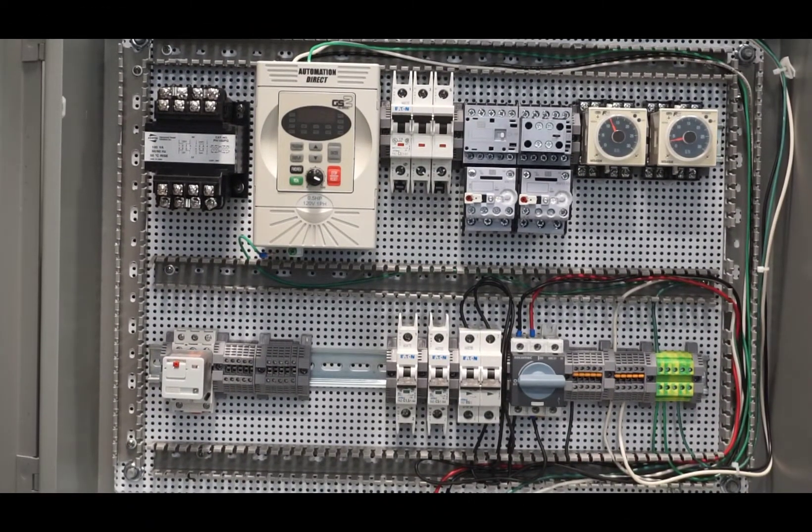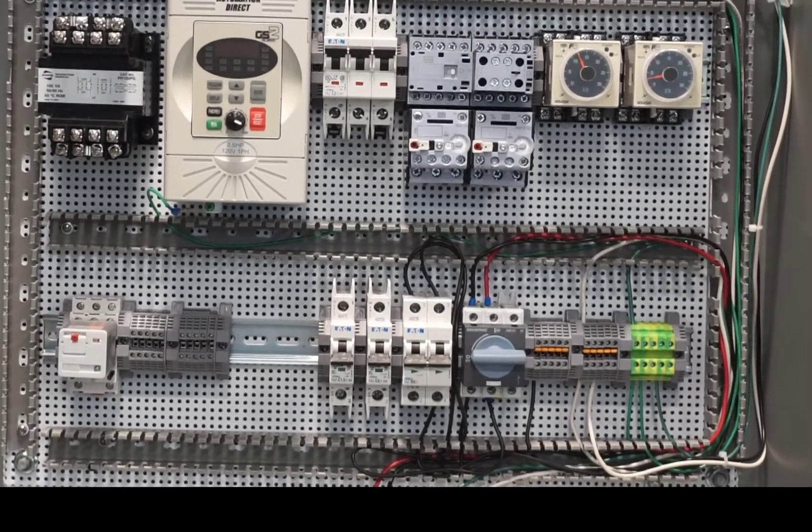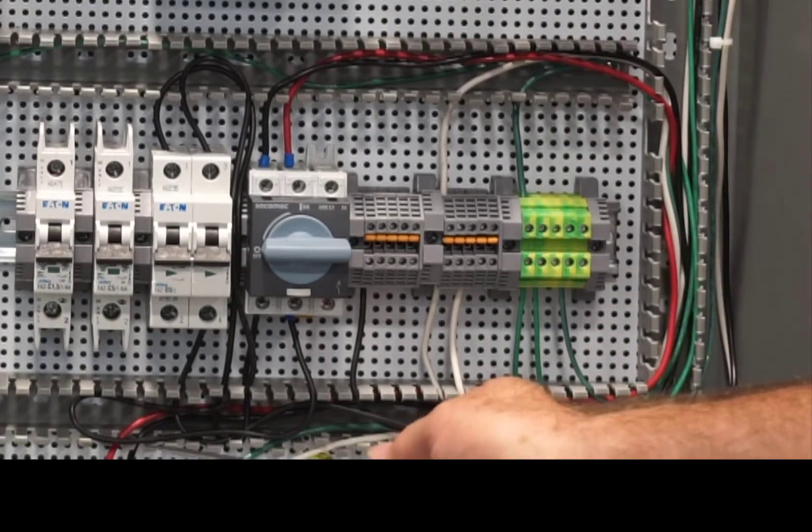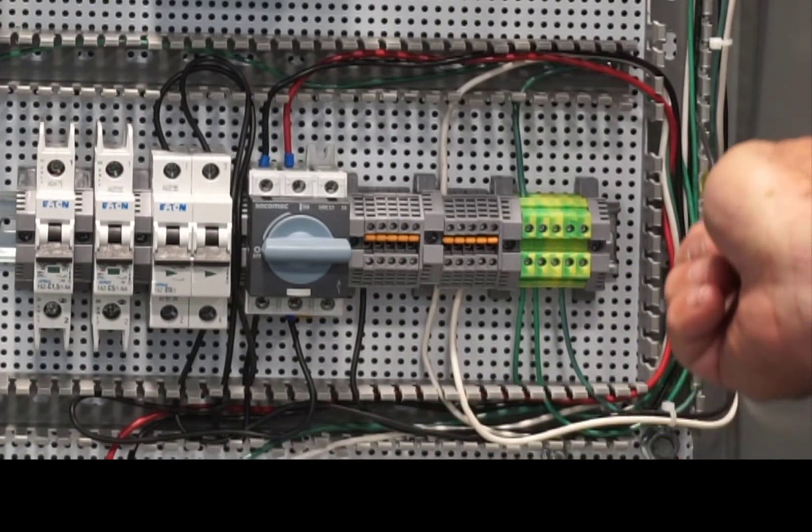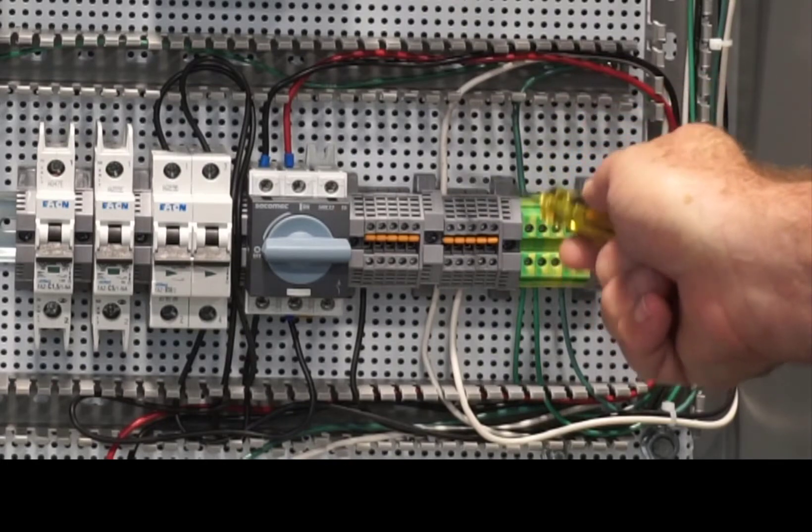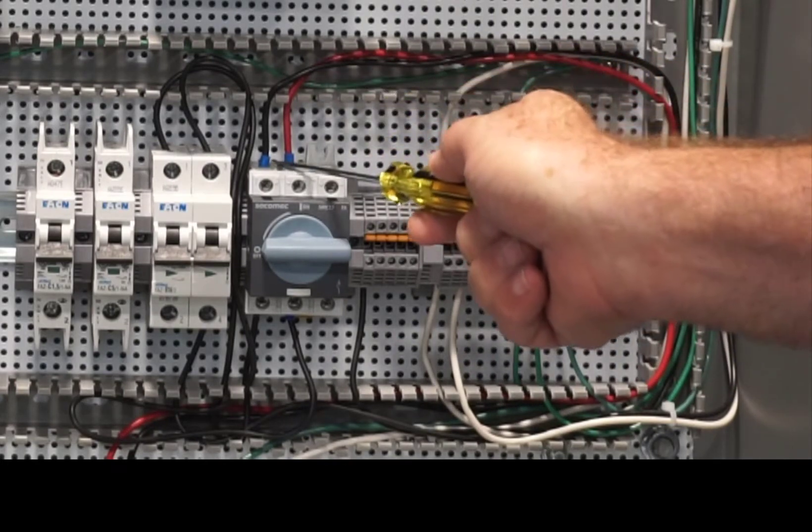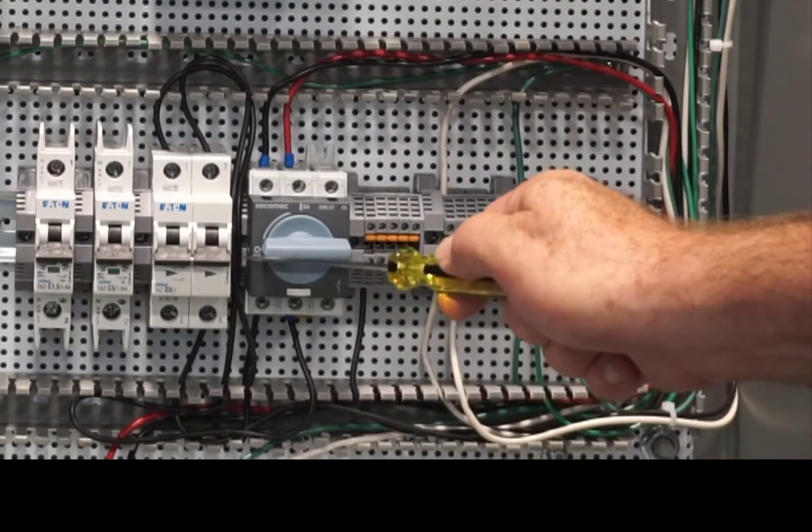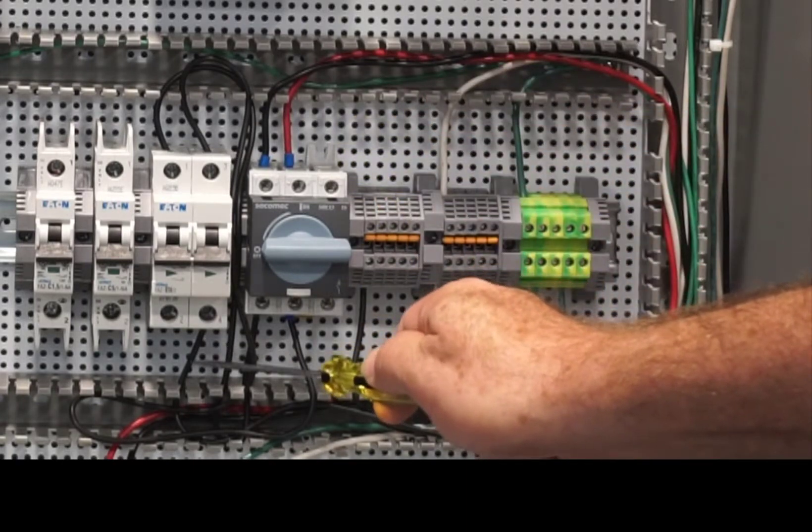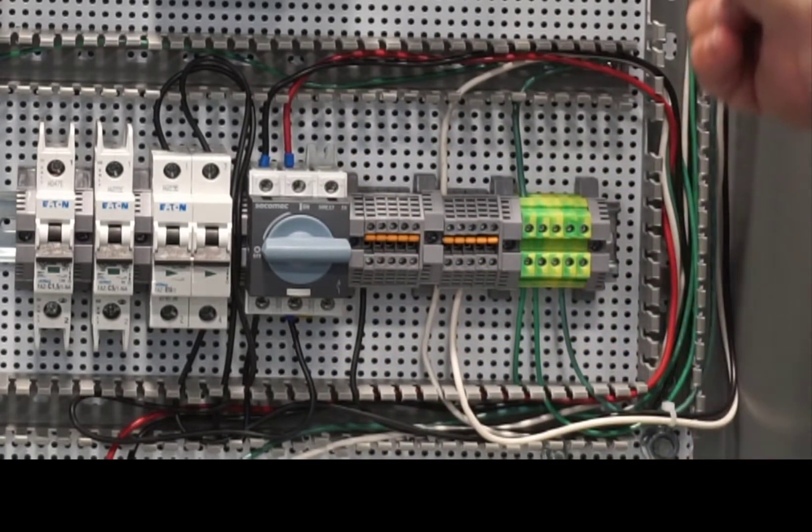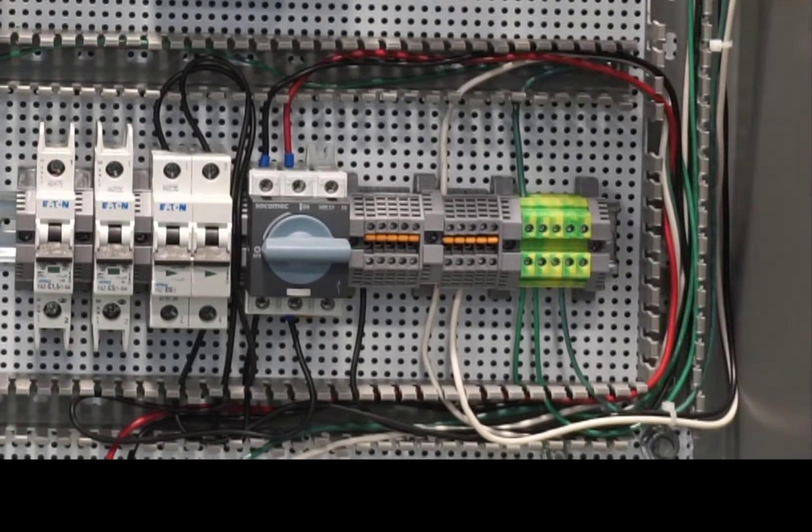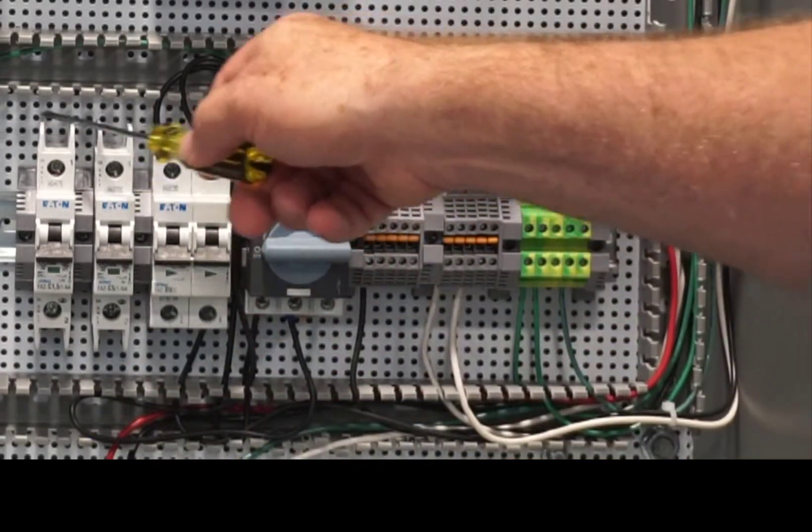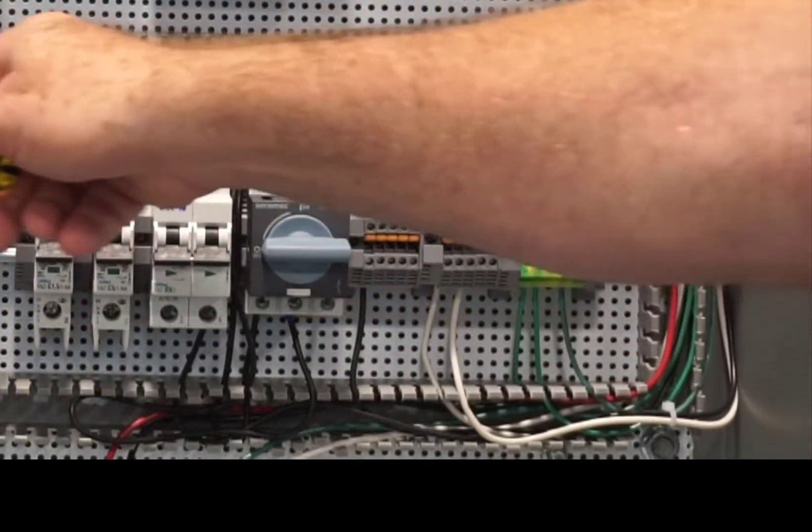Our input power is 120 volts, 240 volts, single phase. You see it enters in here through the bottom and comes up around through here. Our incoming ground, incoming neutral, one line in red and the other line in black. It goes through the disconnect, comes out and connects up to this two pole breaker. The PLC side is on the right and goes directly up to the PLC circuit breaker on the top. Your 120 volt supply will be on the left hand side and these breakers are what you'll be using.